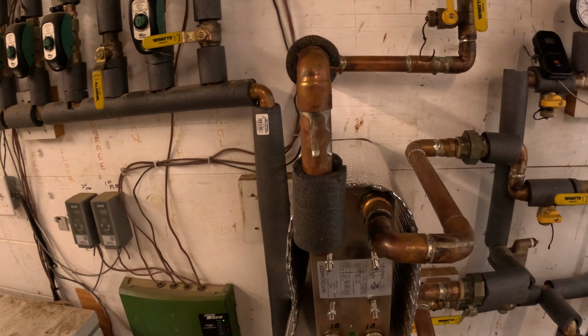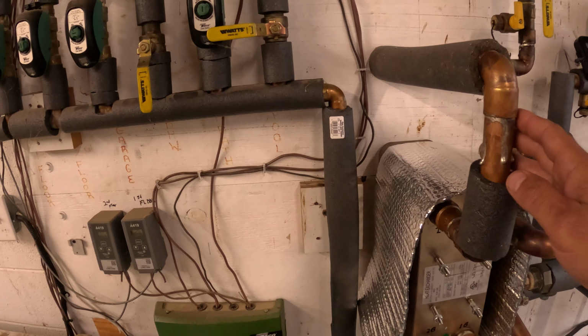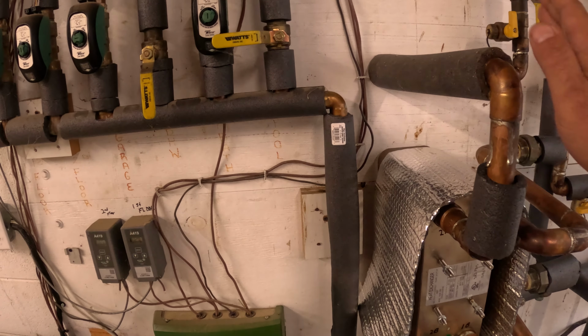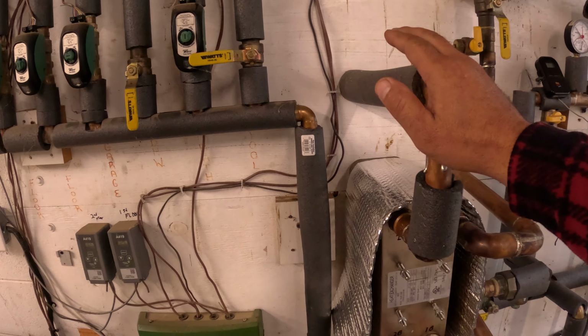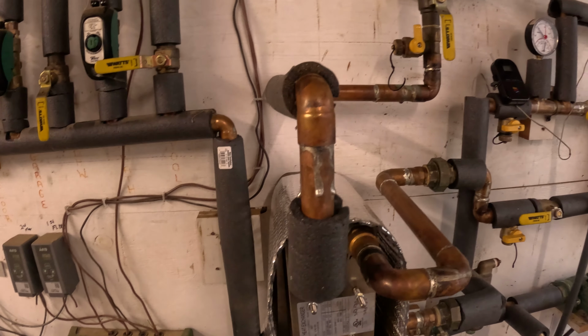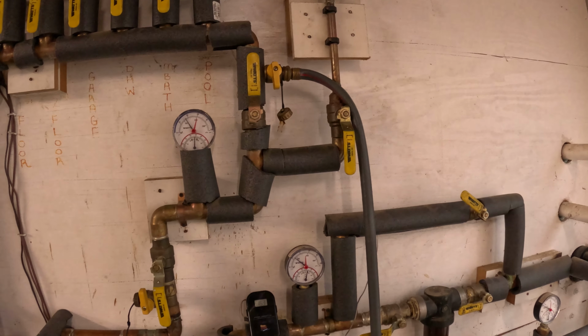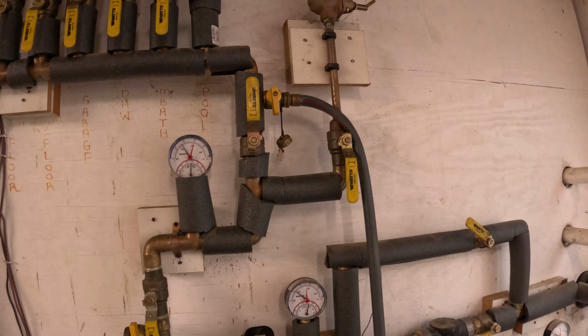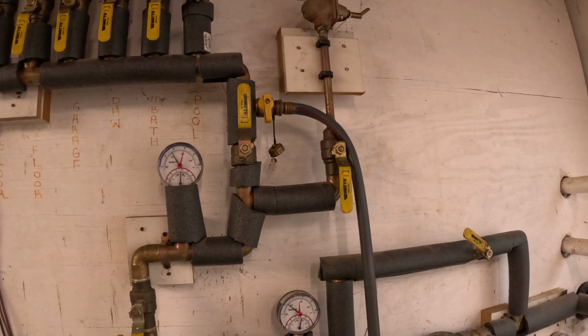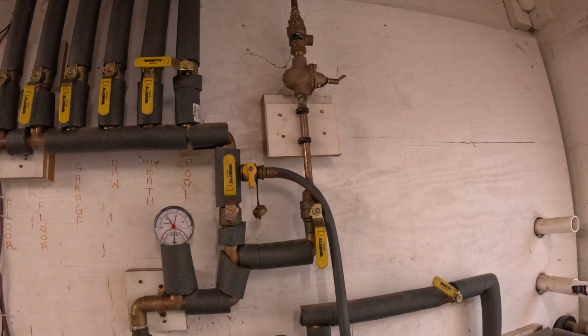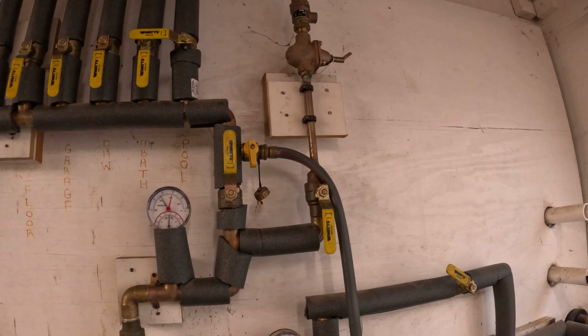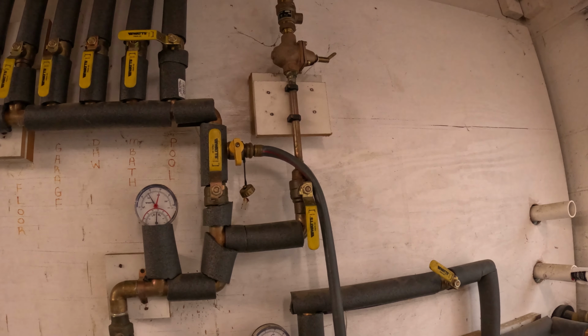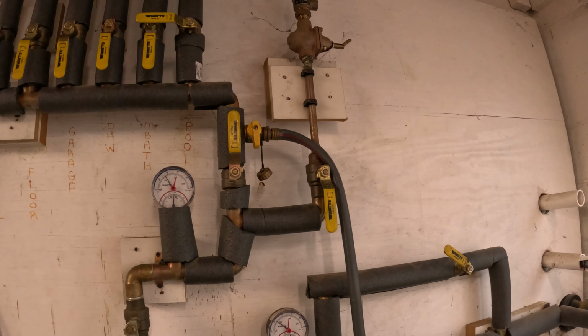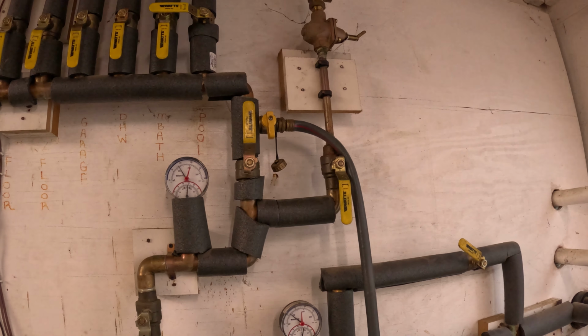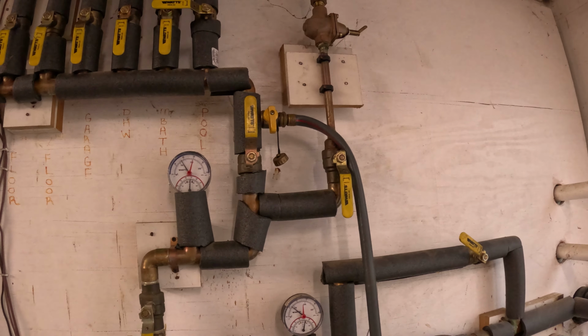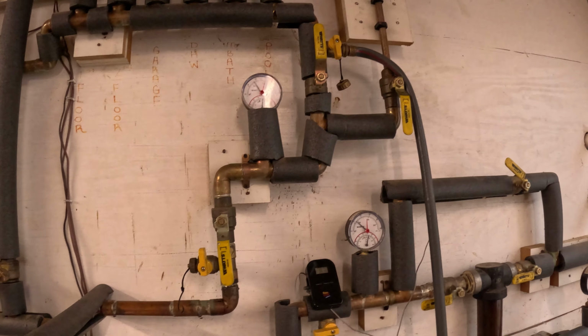Now for the part that's on the house, the heat exchanger obviously transfers the heat from the outdoor wood boiler to here. This is a closed system, meaning that it's pressurized, and essentially we've got this pressurized such that the pressure is what actually pushes the water, from my understanding. I'm no expert on this hydronics, but from what I understand, the pressure, which is, I can't remember if it's 10, 15 psi, I can't remember, but the pressure is actually what pushes the water up, you know, from the basement to what would be considered the 3rd floor of the house, and then the circulator pump just moves the water.